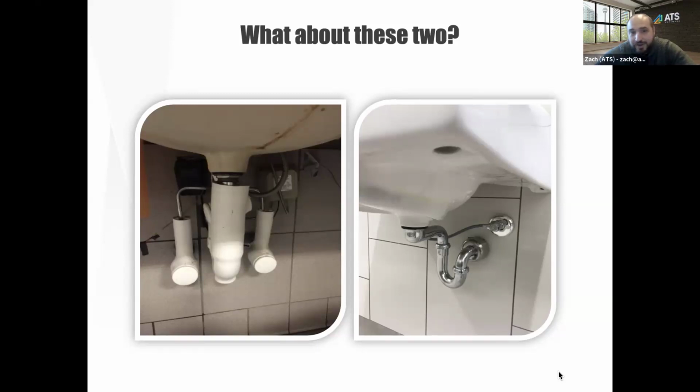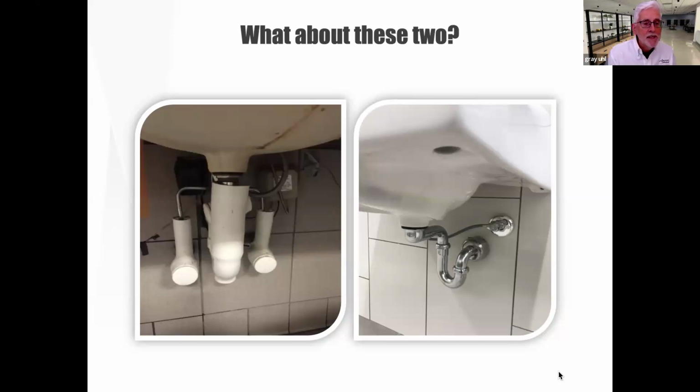I guess the sensor operated faucet on the left, and it could be manual on the right, because you've got the electronic box. Excellent. Very good. You actually did better than what I was looking for. So that's awesome. Yeah, the one on the left, for good reason, but you can see there's a lot going on underneath that sink between the protection, the electronic box, and it's hard to see, but there's also a thermostatic mixing device under there. The one on the right-hand side, oh my gosh, there's none of that. It's all very much cleaned up and simplified.